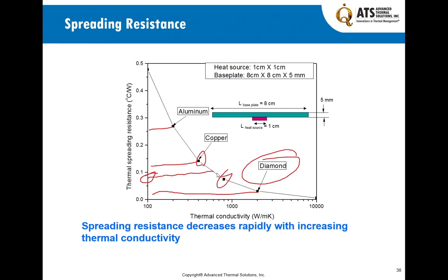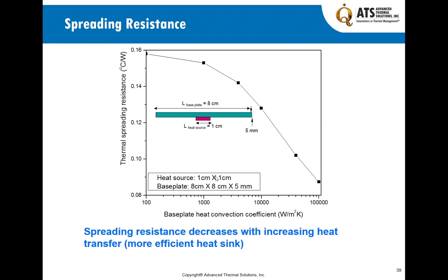Convection also plays a significant role. For air applications with jet impingement we might reach around 1,000 W/m²·K. Most fan-based applications, if well designed, are around 90–120 W/m²·K. To get to 20,000 W/m²·K or more is a major undertaking. In most applications you are at much lower convection levels, and the resistance at that level is very large in comparison to what we saw with cold plates — highlighting the advantage of liquid cooling for high heat flux situations.